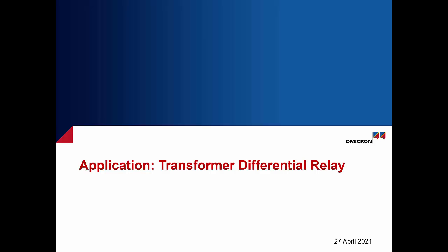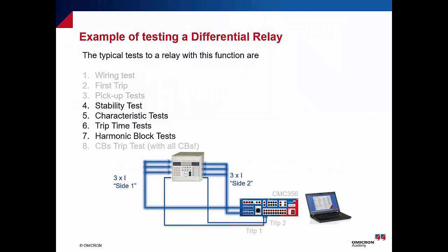Let's go directly to the transformer differential relay, how it is connected to the system, and what the main test points are which we need to check, which are recommended by OMICRON to be applied for the testing or the maintenance of such kind of application. Point number one is a wiring check.